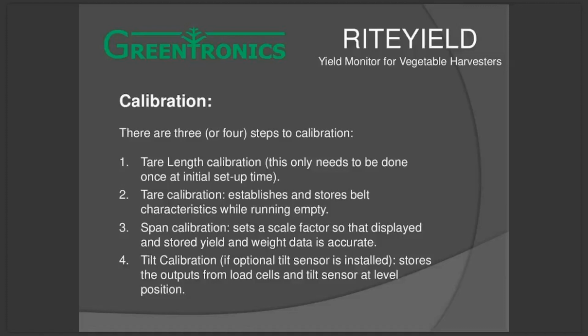Now you can imagine if you run that conveyor for only 2 feet or something, you might end up with data that are not very representative of the rest of the conveyor. So it's important to run it around at least once. But typically, I recommend to people to go 3 times or even more. And that depends a little bit on the conveyor itself, of course. If you have a conveyor with flights, those flights will over time deteriorate. So some flights are gone, some flights are broken. That changes what the conveyor weighs along its length. And in order to get a good reading on that, you have to run that belt quite a number of times around so that the system can figure out what the weight is with nothing on it.